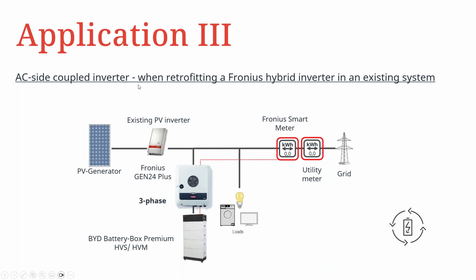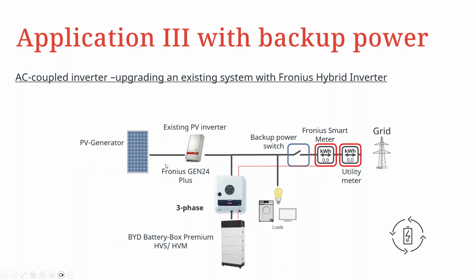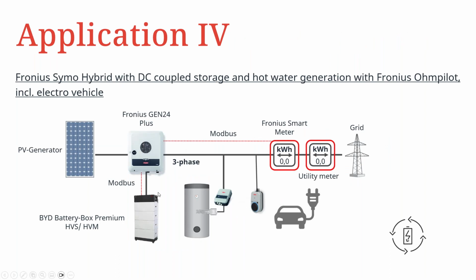We also have the third scenario where we have a retrofitting solution with an existing PV inverter, as you can see. And it also comes with an improved version of that retrofitted system, in this case, with a full backup system and with a backup switch implemented. It is also possible to have a fourth scenario where we have a grid-tied system where we make use of surplus energy, not only to charge the battery for later use, we can of course generate hot water for later use also, and then have our EVs sufficiently charged with the most economical means possible.